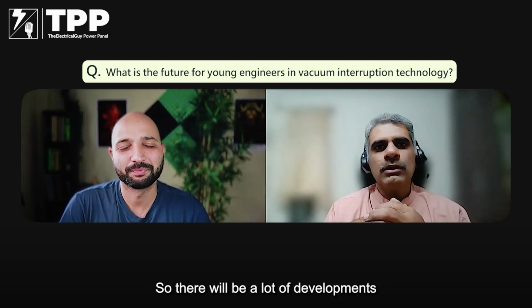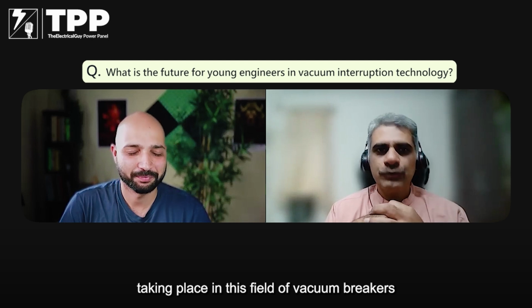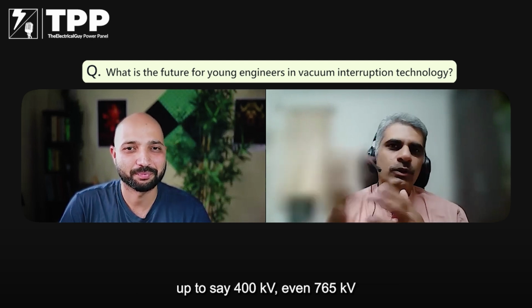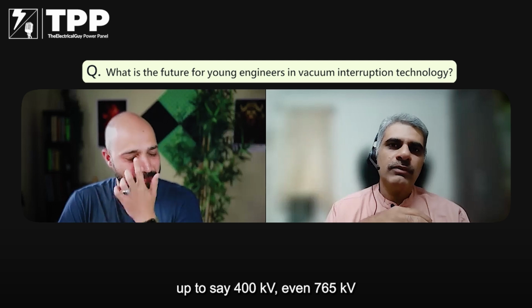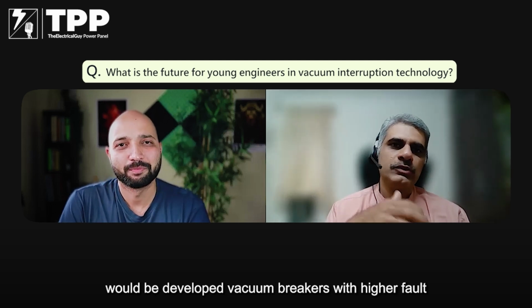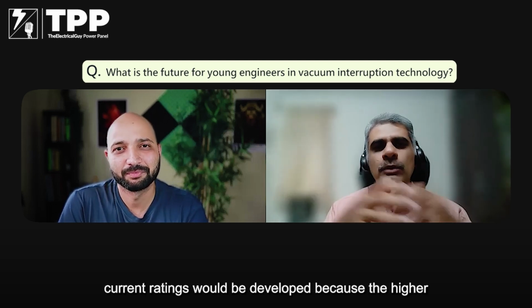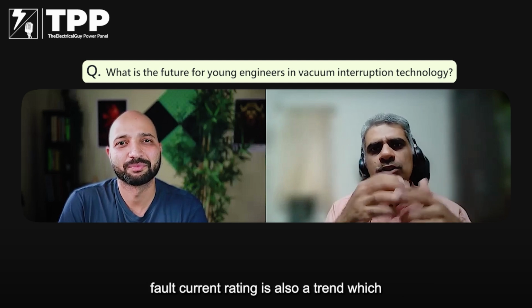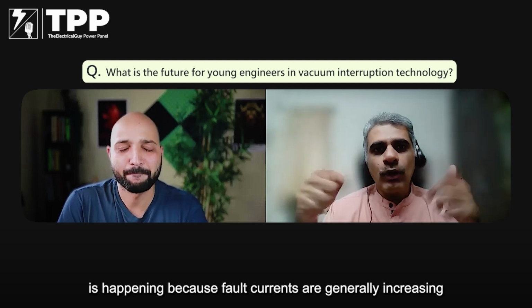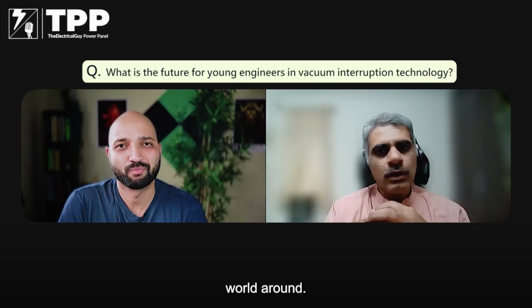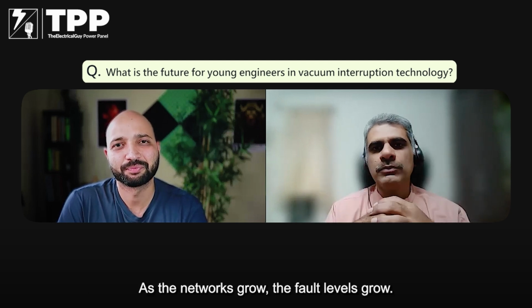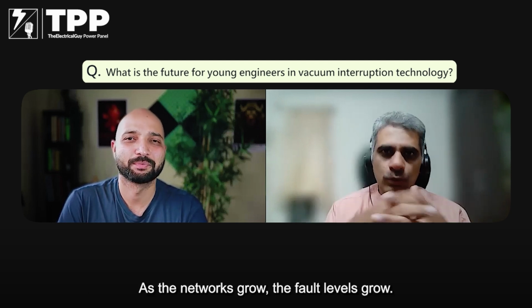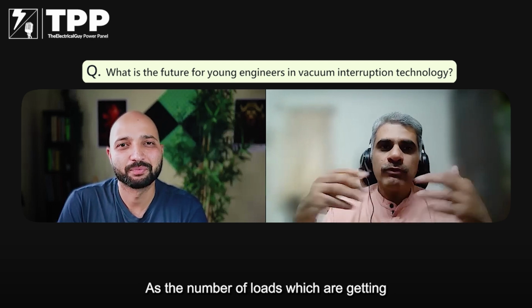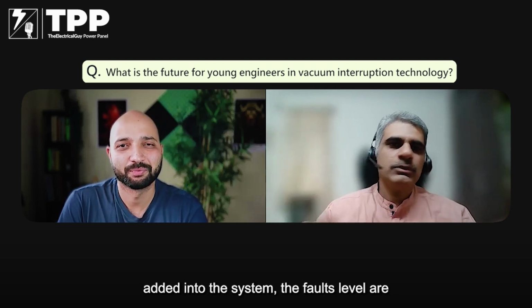So there would be a lot of developments taking place in this field. Vacuum breakers up to say 400 kV, even 765 kV would be developed. Vacuum breakers with higher fault current ratings would be developed, because higher fault current rating is also a trend which is happening, because fault currents are generally increasing around the world. As the networks grow, the fault levels grow. As the number of loads which are getting added into the system, the fault levels are growing.